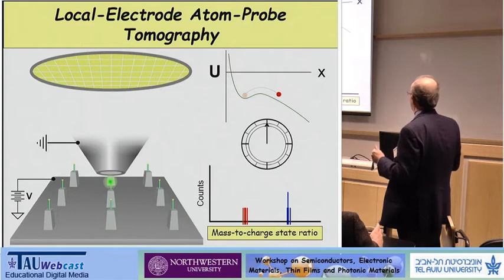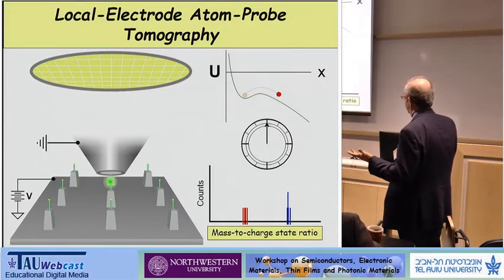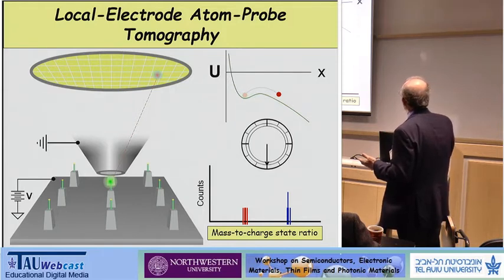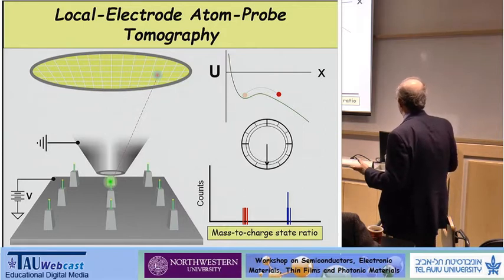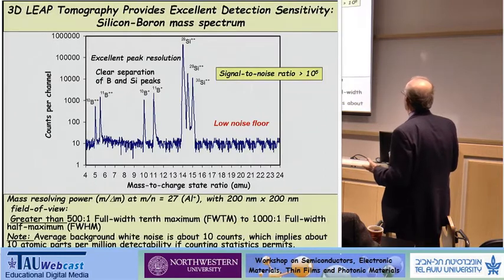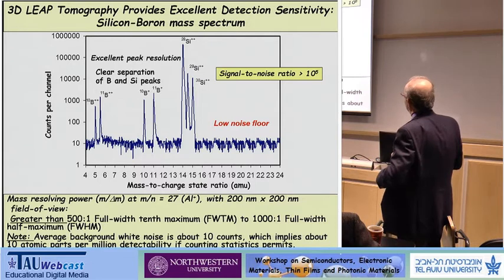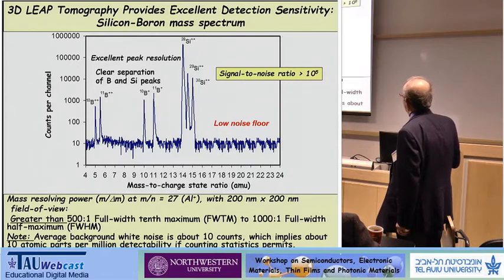Okay, and here's another cartoon showing how it works. This is the so-called local-electrode here that you're looking at, this conically shaped device. These are silicon nanowires, say, a little bit of gold on the top, the gold catalyst, and then you evaporate. You hit them with laser light, and you can see over here what happens. This is the potential energy of an atom at the surface, and it's field evaporated over this Schottky hump, and it becomes ionized. And then you collect the mass spectrum. Every time it hits the detector, the output is a mass-to-charge state ratio, and you count and you can identify the isotopes. And here's a simple example for a silicon-boron alloy. You can see the 3 isotopes of silicon here in the doubly charged state. You see the 2 boron isotopes in the singly charged state. And here you see boron in the doubly charged state. And if you look at the background here, this is counts per channel.